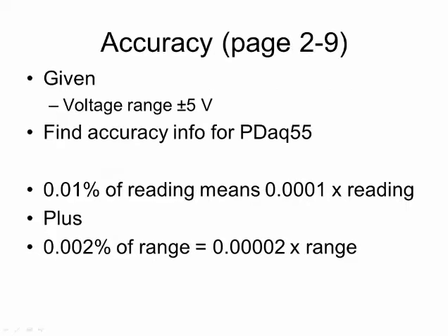Please find page 2-9 of the PDaq55 user manual and find the section labeled Voltage Specifications. The first line is labeled Accuracy. The information here indicates the uncertainty of the PDaq55 output for a given analog voltage input. The information is in the form of an equation because the uncertainty depends on the voltage reading and the voltage range setting of the PDaq55. You can select the input voltage range for each analog input channel, so it makes sense to have an equation with voltage range as a variable.